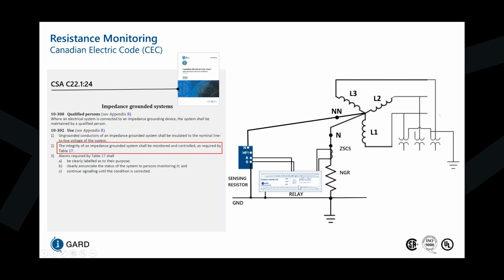The reason why we're using a high frequency signal is because the windings of a transformer or generator are typically modeled as inductances. And because our inductance is XL equals 2 pi FL, with a high enough frequency, this inductance becomes a higher impedance than the NGR itself, such that the majority of our signal will take the path down through the NGR and back to the relay. Now, our relay also has a DC-based superpositioning on this high-frequency signal to also do DC-based injection through the NGR. And that's an additional measure utilized to combat a lot of capacitance in the system.